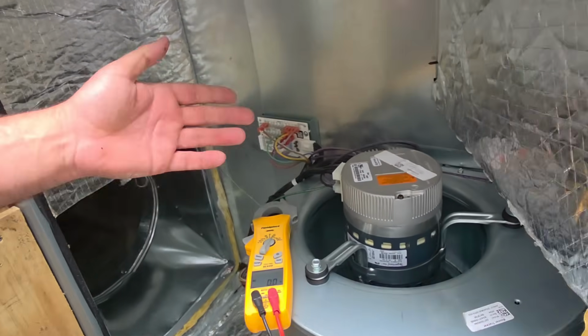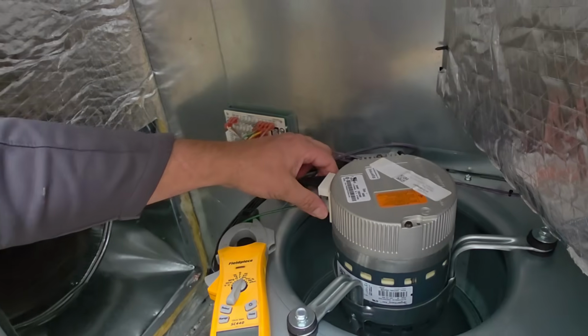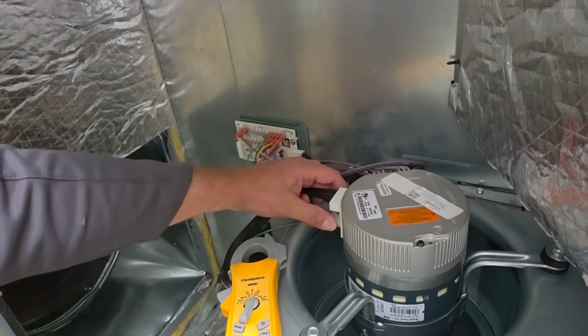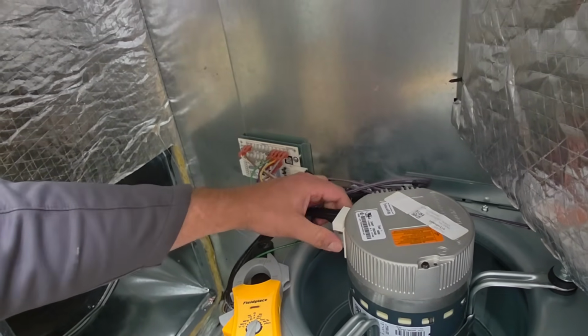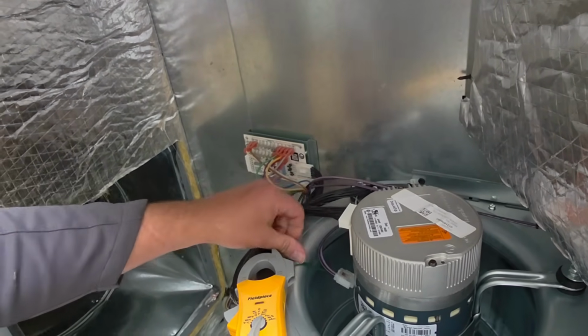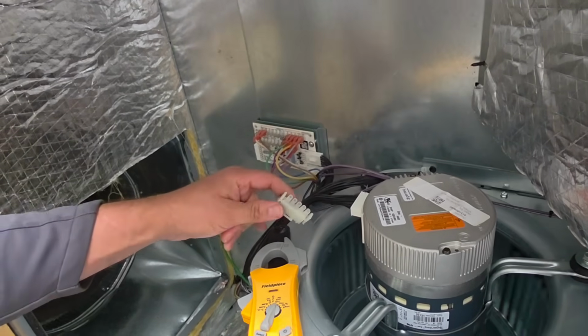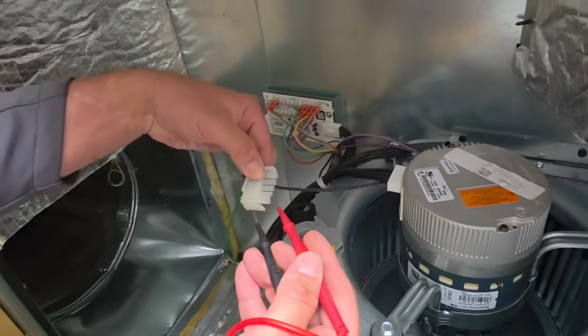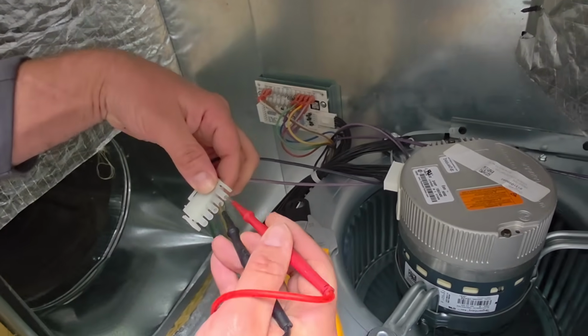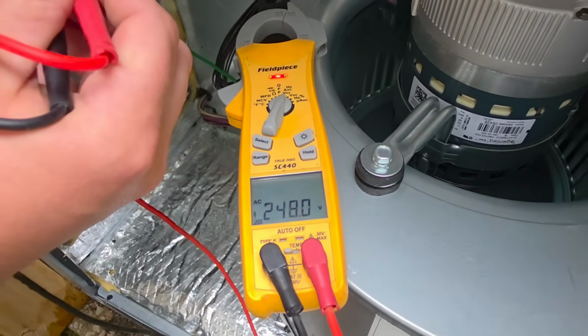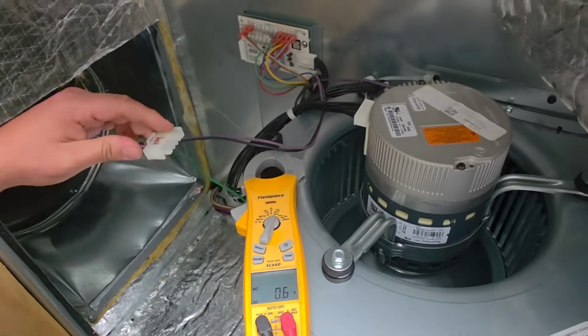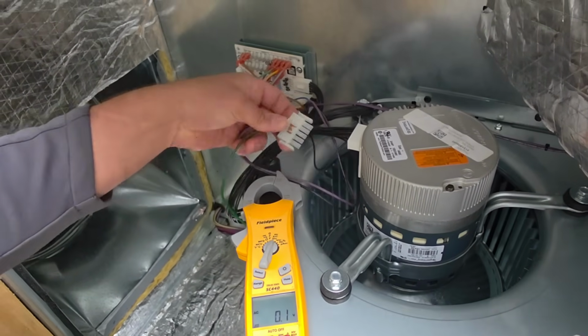Now let's check the call to the motor. We should always have 240 volt going to that motor. Let's unplug it. By the way, make sure you disconnect the power before you do this, I want you to be as safe as possible. Volts AC, purple and black, we should have 240. We do, all right, so we got that.